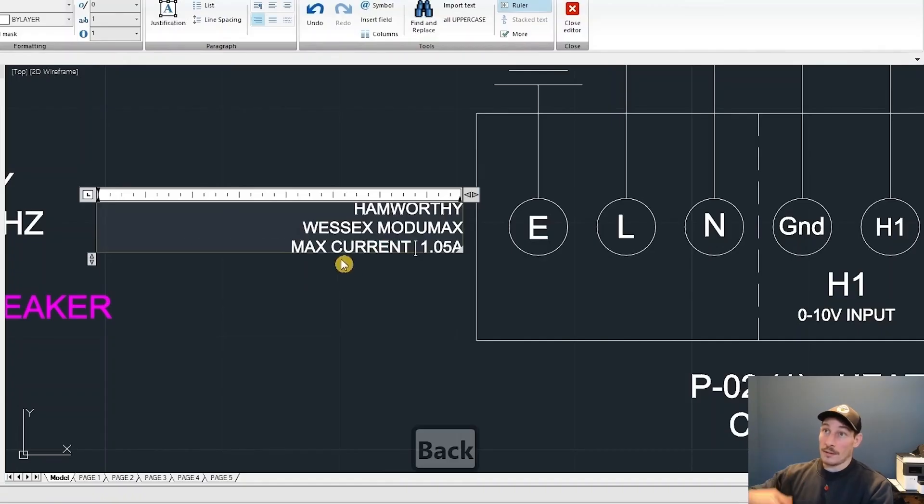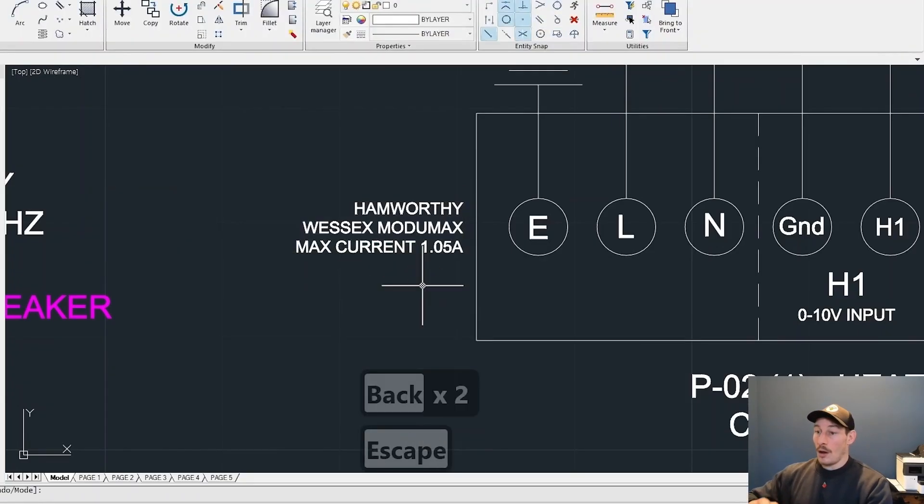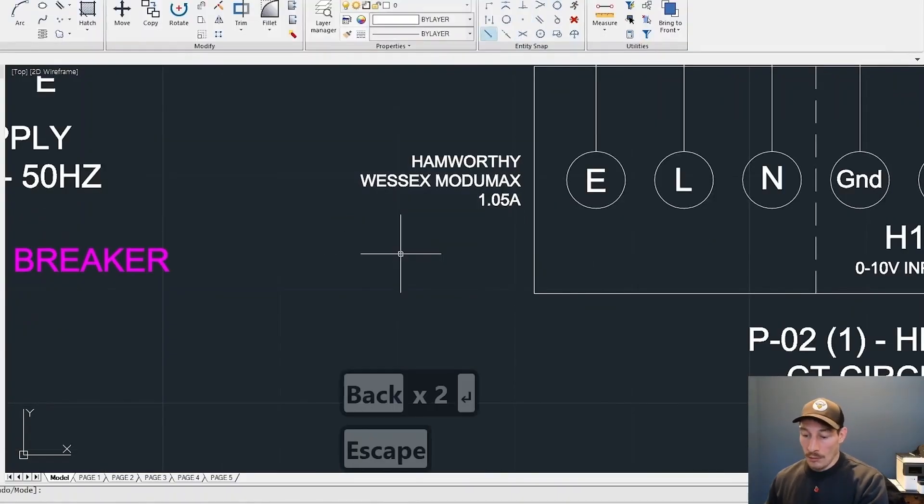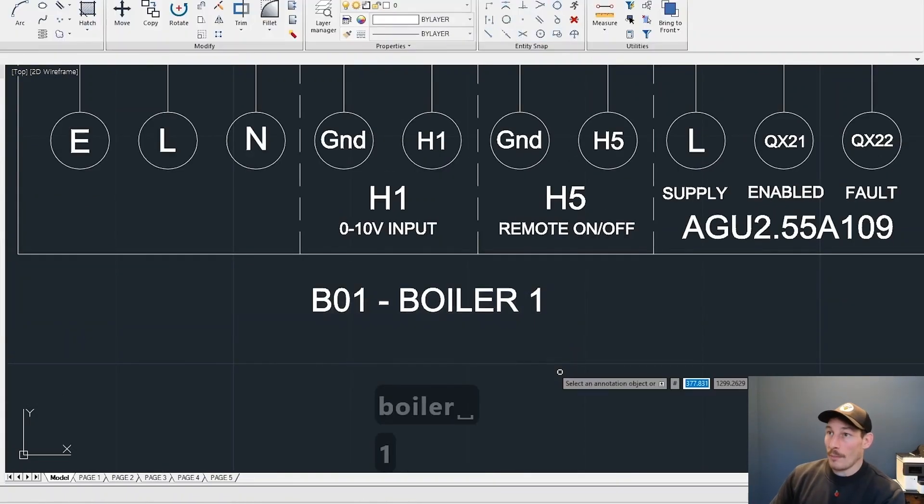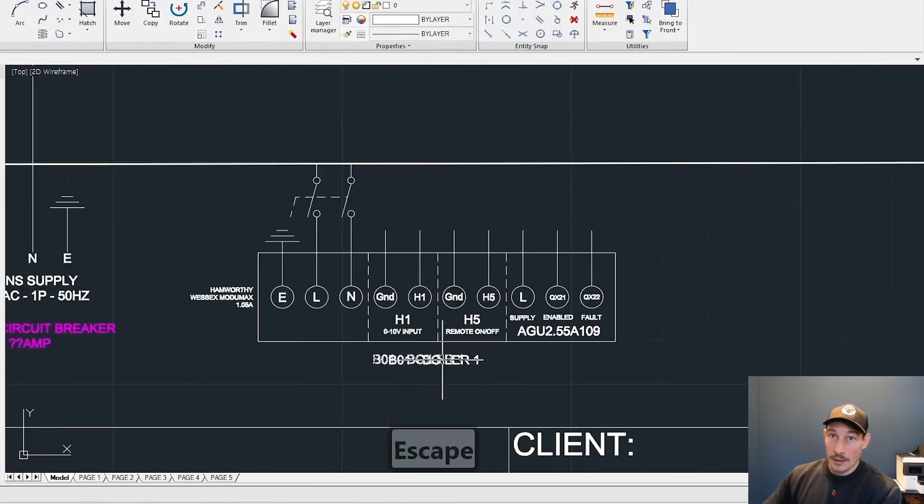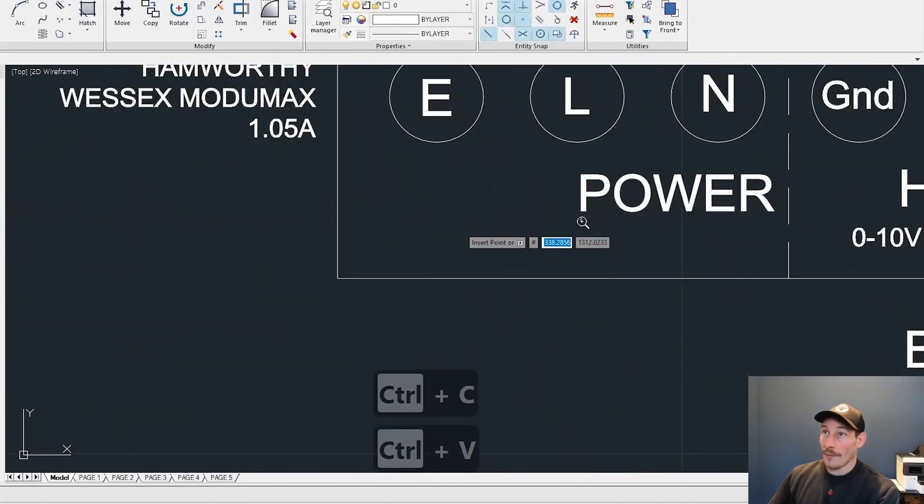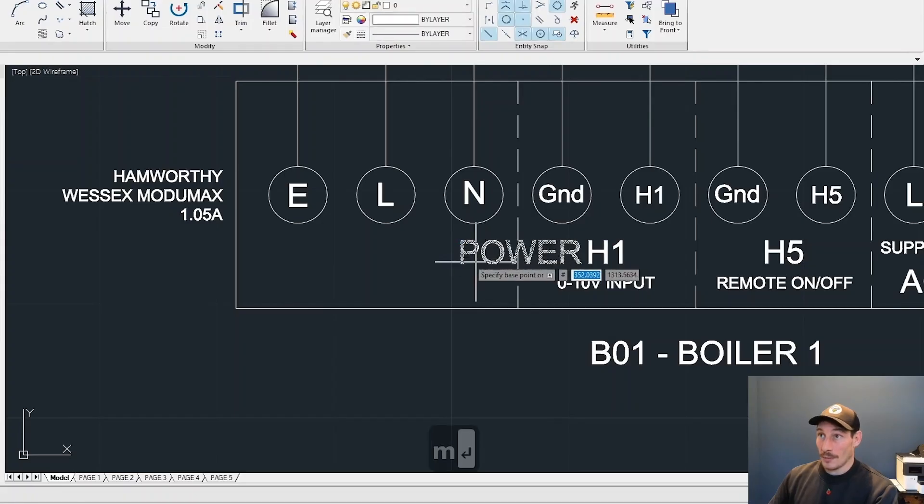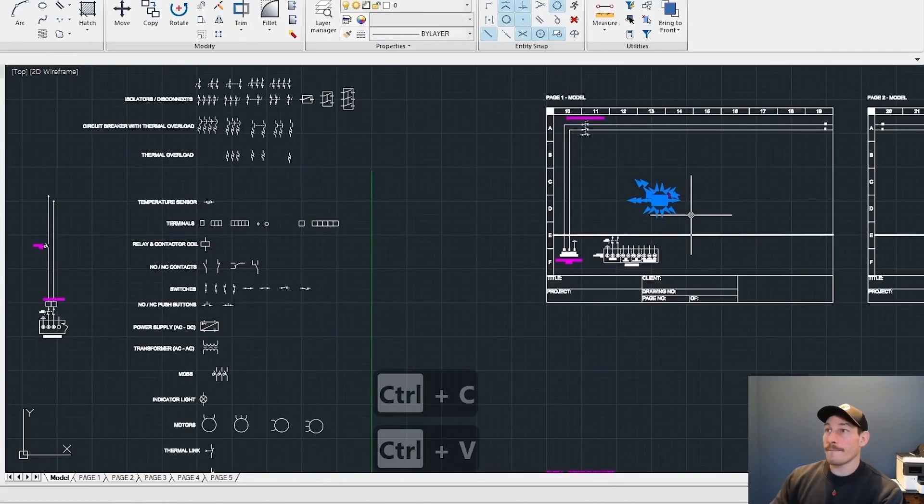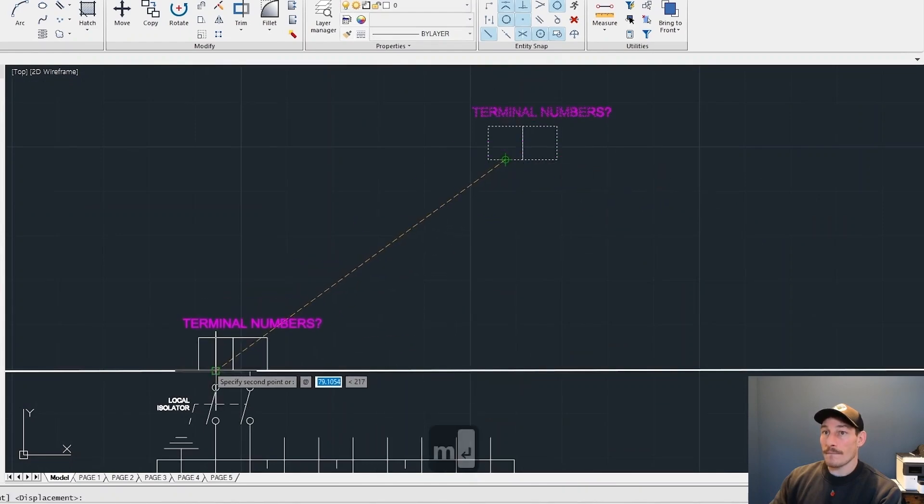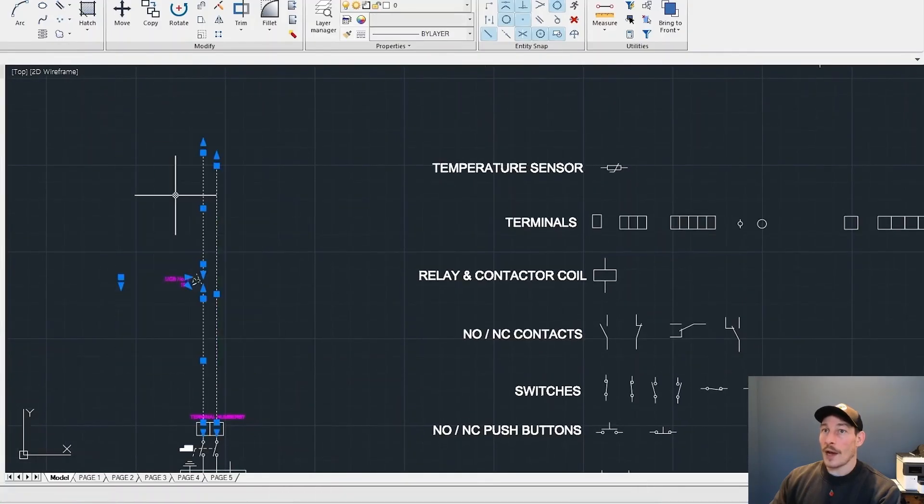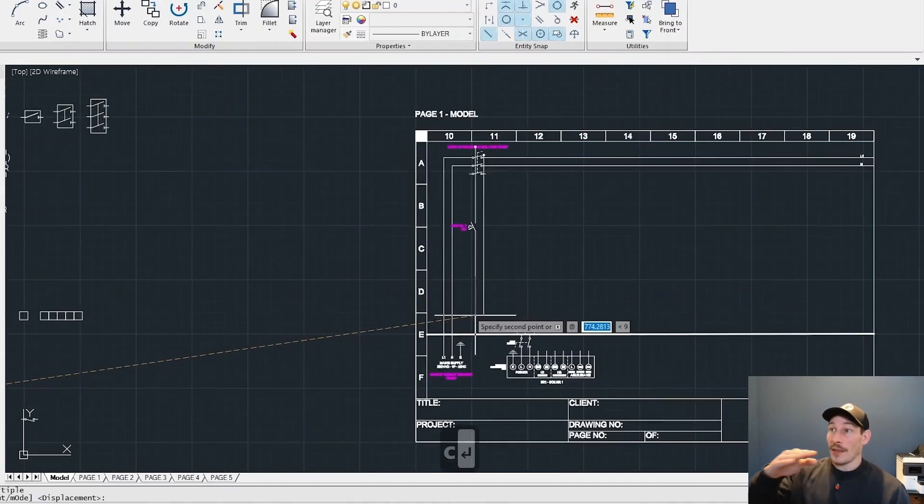Once we've done all of this for all components, we can add up the total current draw for the main breaker or the main supply. Just so we have got enough power being supplied to the panel, to the system. If everything's on, we want to make sure that there's enough power being fed to it.